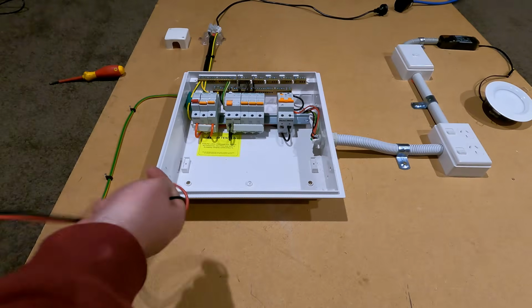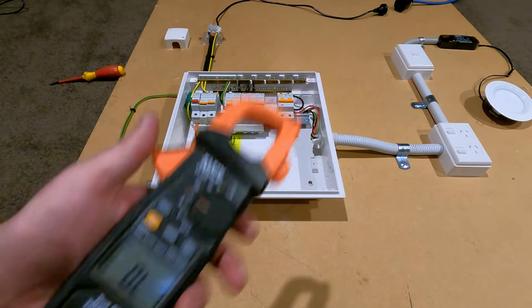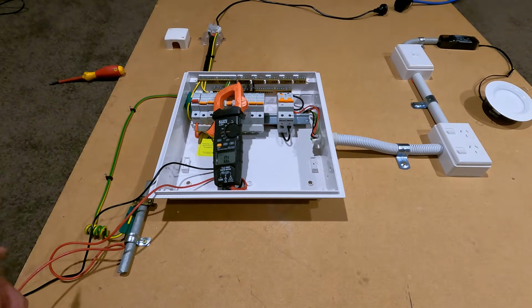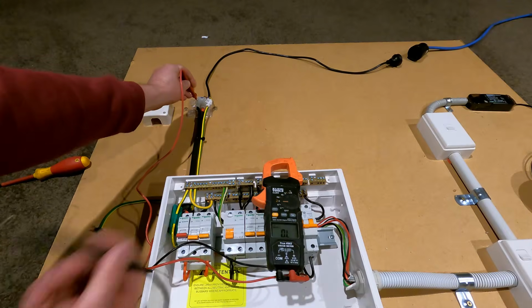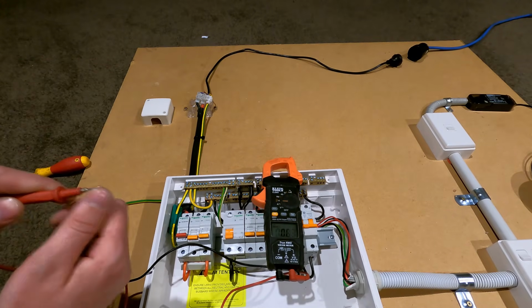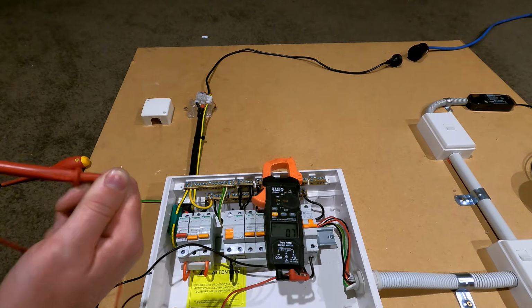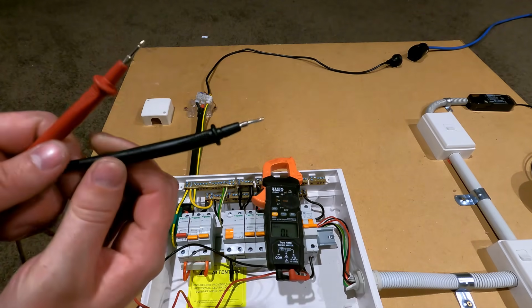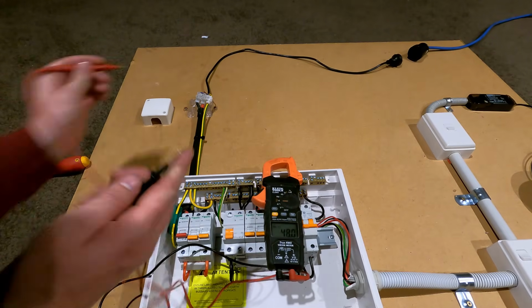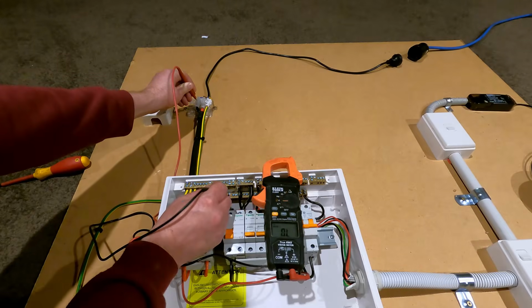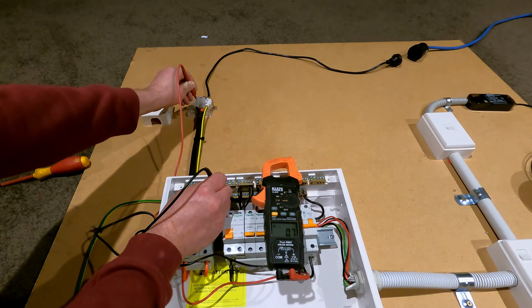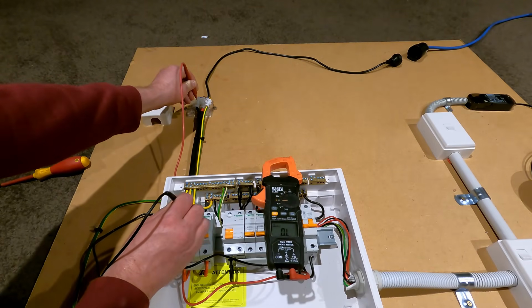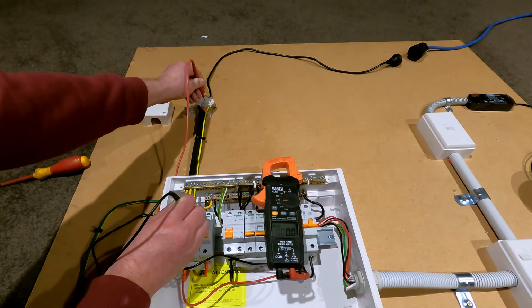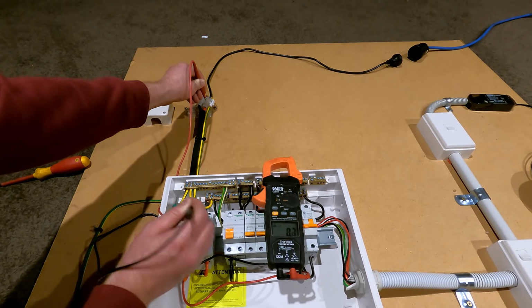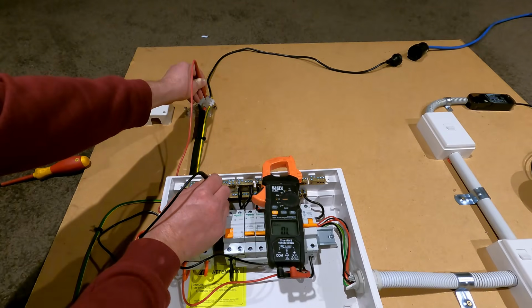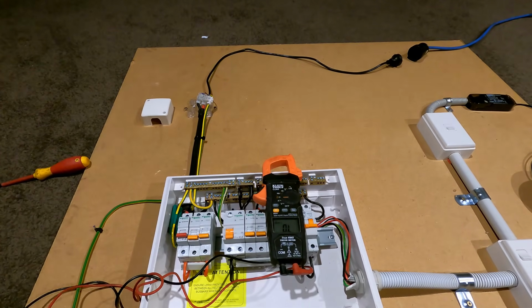So what we do for that, we can put it on continuity or on ohms and just check the resistance or check the continuity. We're going to make sure that the neutral over here goes back to the neutral bar. So we'll put these together, see what we're working with first. 0.7 ohms. These meter leads have had their day and they'll probably be getting binned next week. So with that in mind, just check the neutral goes back to the neutral bar. So we've got our 0.7 ohms there and nothing between that and phase. And then we check our phase. 0.7 ohms there. And of course nothing between phase and neutral. So that's our polarity tests done on the mains.